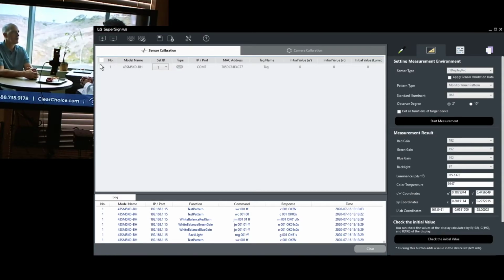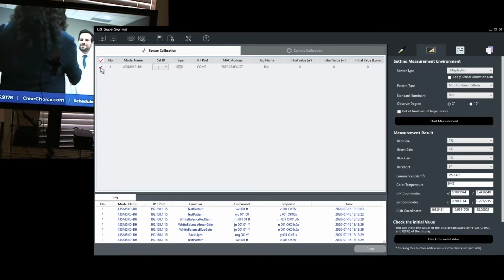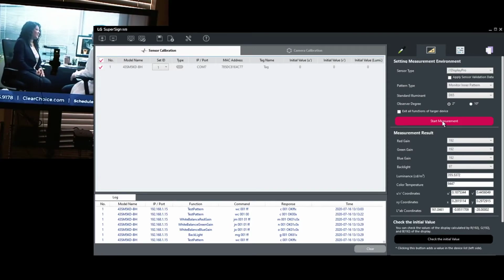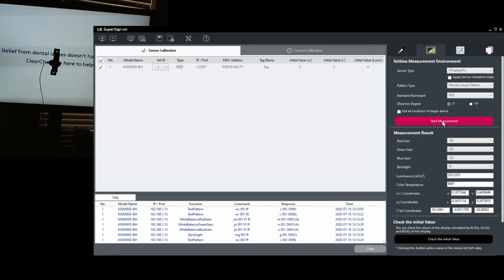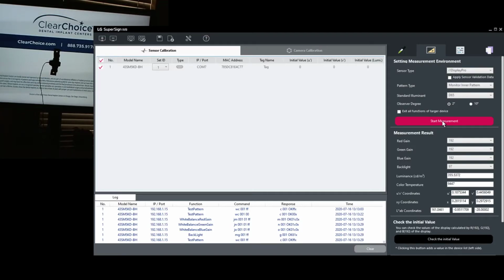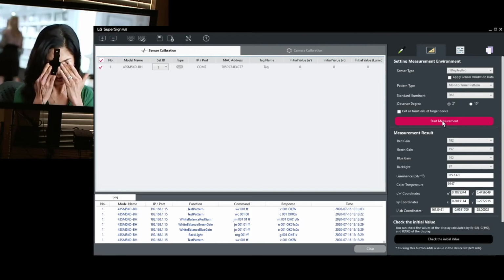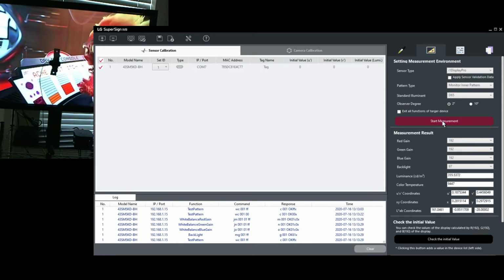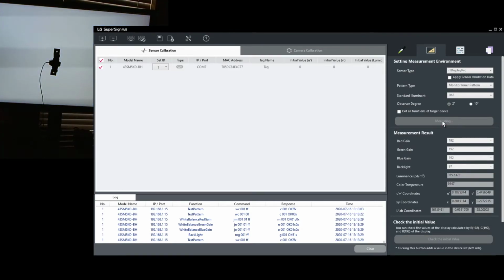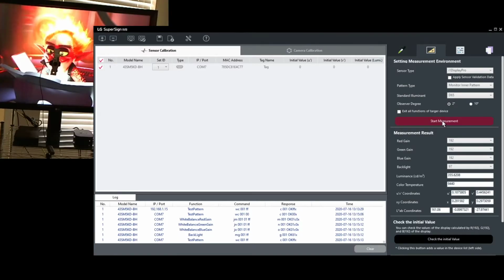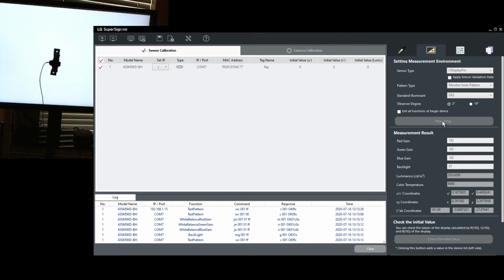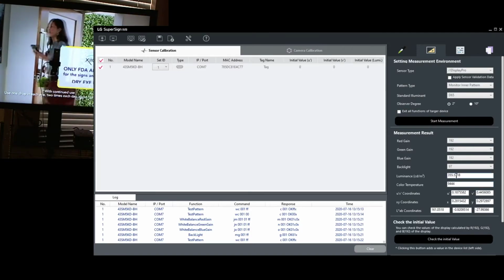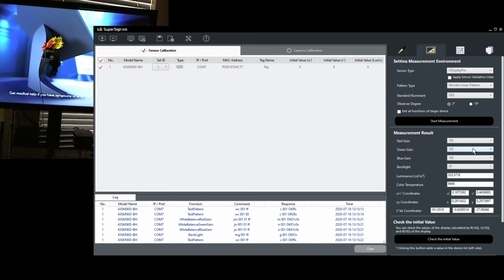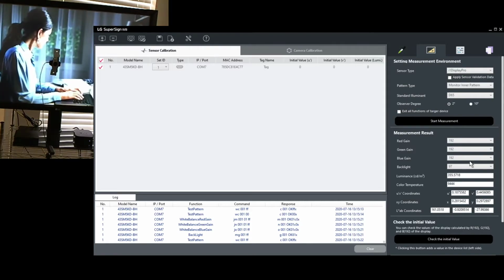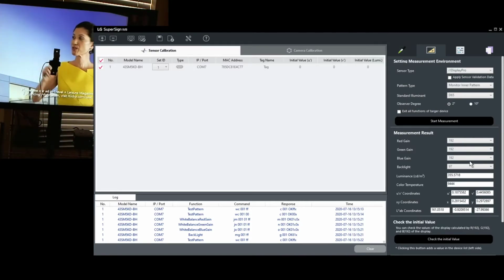So here's the interesting thing. Now that we're doing it over serial port, we're going to see a little bit of a difference. So I'm going to select the display that I'm going to communicate with, and I'm going to do a start measurement. Notice the values on your screen. Red gain 192, green gain 192, blue gain 192, backlight at 97, and luminance at 355.5372, color temperature 9447 Kelvin. So let's start our measurement. Now our measurement says that we're at 355.5718 and then 9444 Kelvin. So there was some variation between that sensor and the display being read through serial and the LAN network.